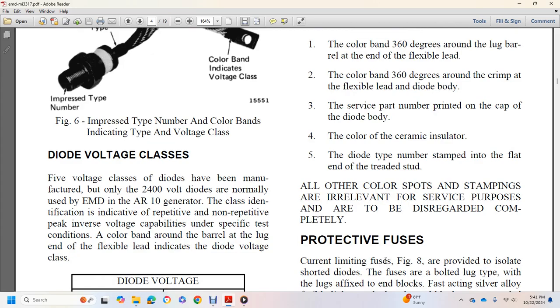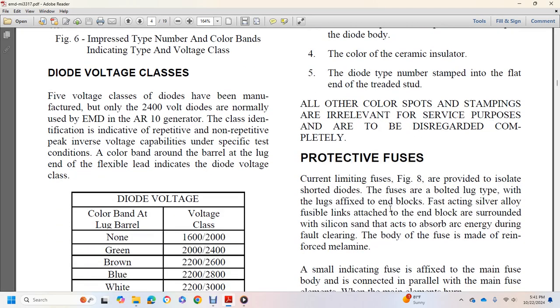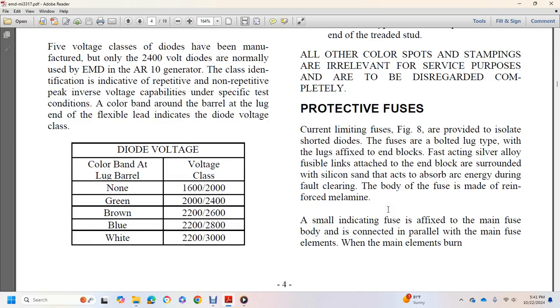All other colors, spots, and stampings are not relevant and serve no purpose; disregard them. Protective fuses: the current limiting fuse, figure 8, is a bolted lug type with the lugs fixed to the end block, with a fast acting silver alloy fusible links attached to the end block and surrounded with silica sand to absorb the arc energy during the fault clearing.